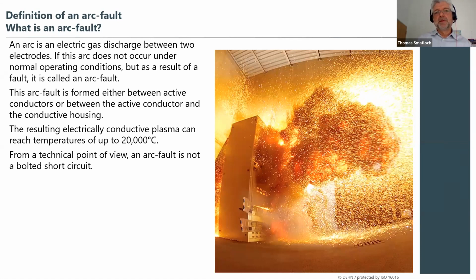When there is an arc fault, there is a discharge via a plasma practically, and this plasma can reach temperatures up to 20,000 centigrade, which is a big threat for installers working in such an installation. From the technical point of view, an arc fault is not a bolted short circuit, because it has a certain impedance. This conductive gas has a certain impedance and is also influencing backwards the actual current flow in this case.